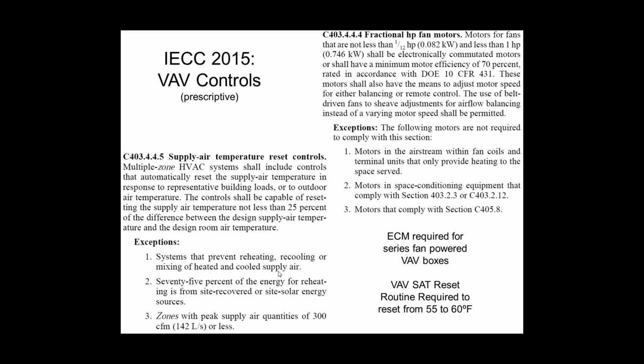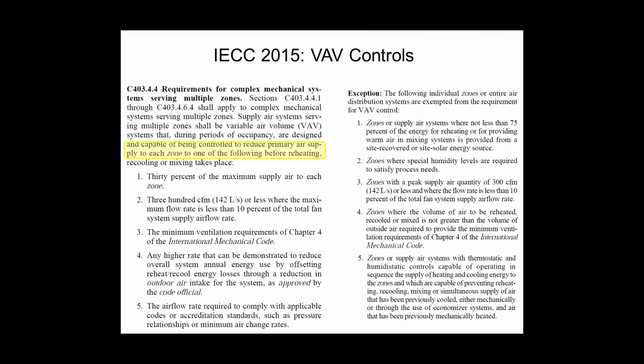So that's kind of the deal on those. This one's been in here for a very long time. People still don't understand it. There are rules that prevent you from reheating air. And by the way, if you heat air that came from the quote-unquote cooling economizer, that is still counted as reheating it. So it does allow reheat for VAV systems.